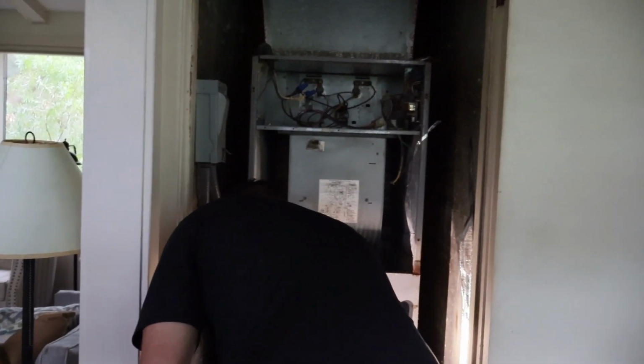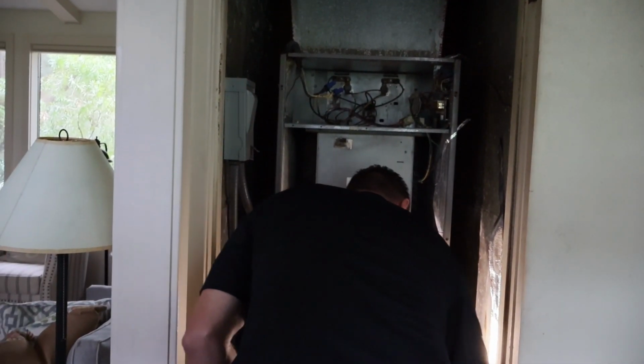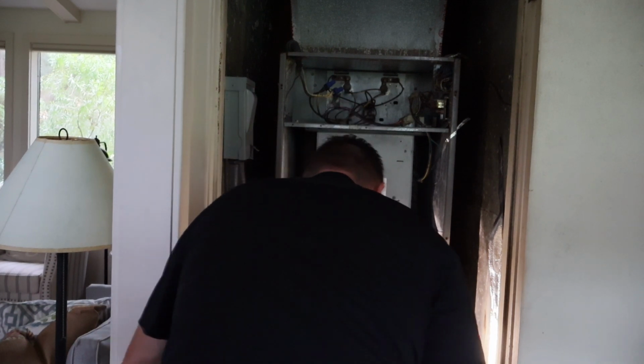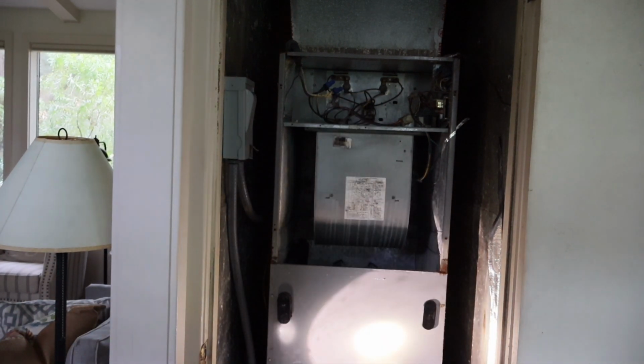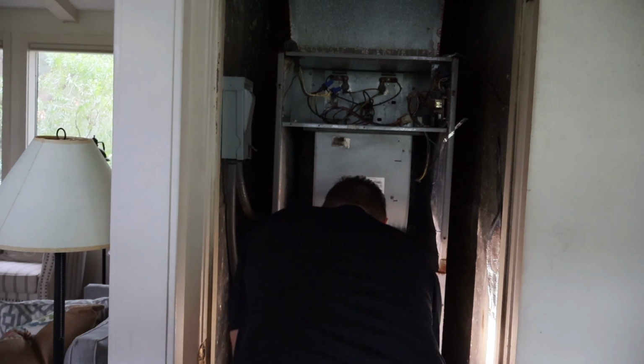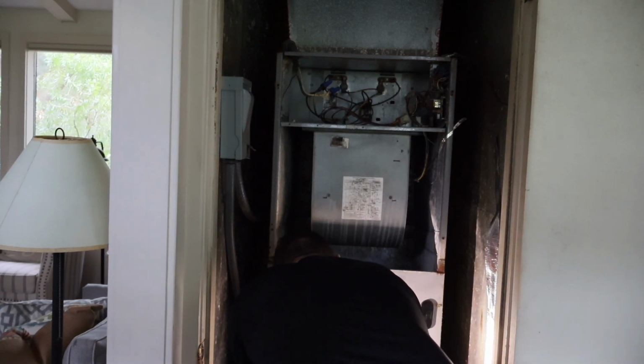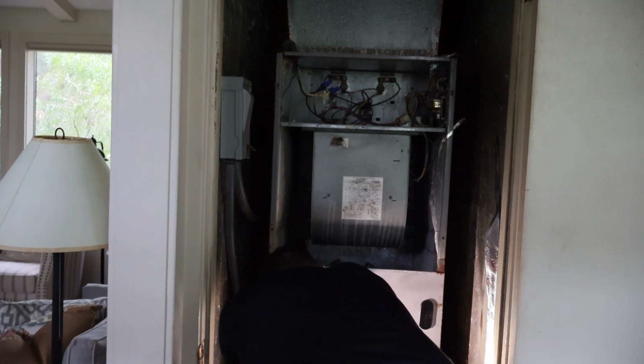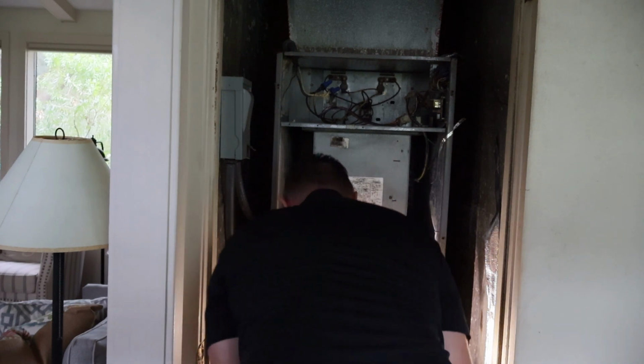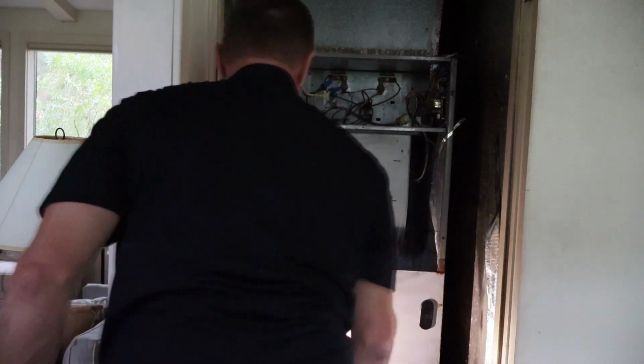And there's a few things that we found that probably will be in the next maintenance that we do. Like the coil, it's got some buildup on it, so it probably needs some attention. And I'll make sure it gets done on the next maintenance. Capacitor's a little weak. Right. Contactor's a little worn. This thing is, I think, 12 or 15 years old. It's got some age on it. So we'll address that, and I'm probably going to come out with them on the next maintenance too.